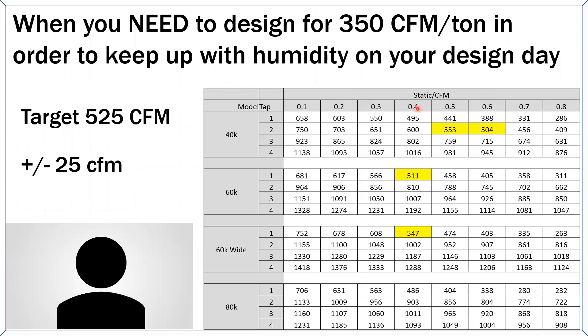What happens if I need the 60,000? You don't, you're in Texas, so don't worry about that. But what would happen if I needed this one and had a duct system that was large and was going to have 0.5 or 0.6 inches of static pressure? 0.4 isn't a whole lot. That's not a very powerful fan, right? And here's another option, right? If I want 875 CFM, I hope you're using the 60,000 wide, because anything else is going to be operating at 0.7 inches of static pressure. Jason, that conversation we were having about watts per CFM, what do you think that does to that? That is not good. No. Right?